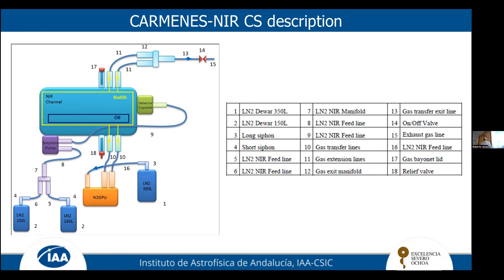It has only two states, open and closed. When closed, the gas remains inside the instrument exchanging heat with the radiation shield. When we open it, the gas refreshes the lines, coming in with new cool gas. So the working mode is opening and closing the valve all the time, and with a PID, an automatic method, we keep the temperature as stable as possible.